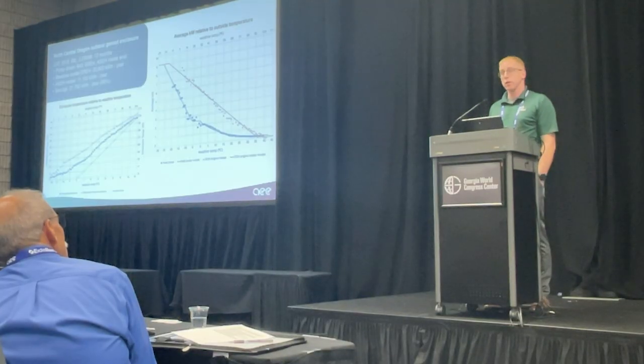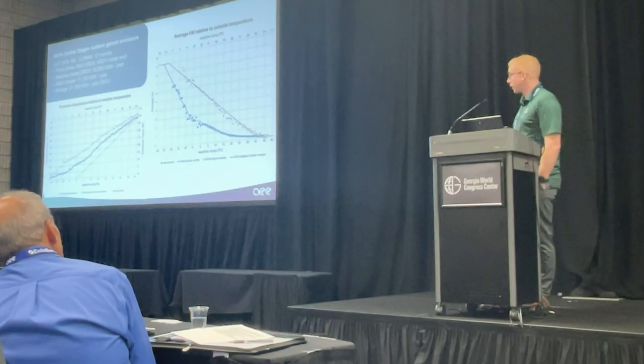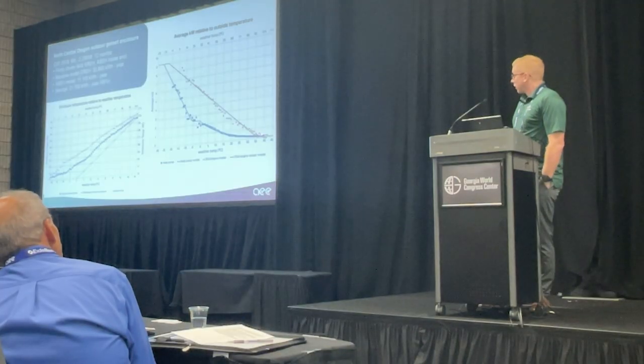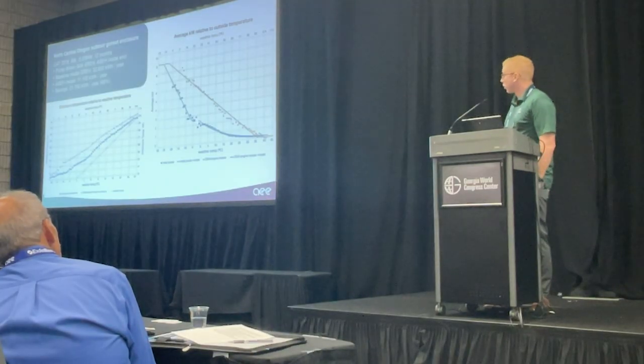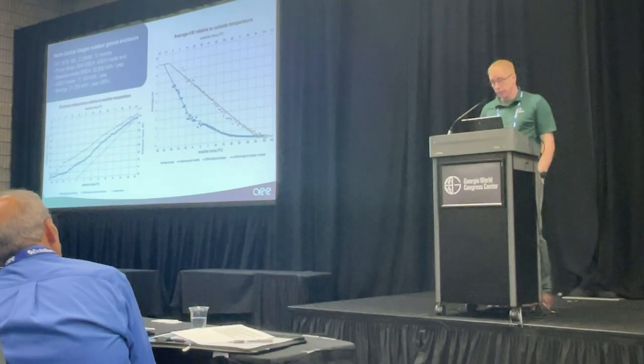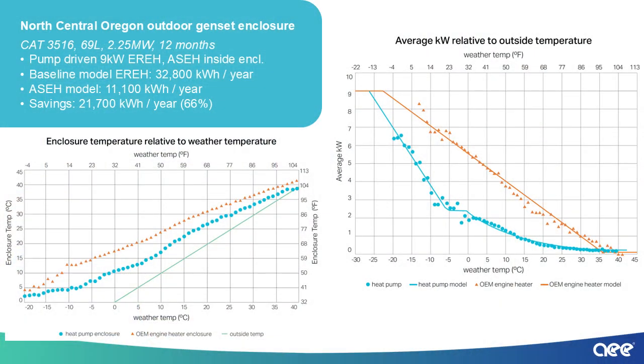So if you're looking at the efficiency, if it was installed outside instead of inside, it would have operated more inefficiently, because you benefit inside the enclosure from the higher temperature, which improves the COP. Data was recorded over a year, so we have a more complete model of this particular unit. You can see essentially the curve is more reminiscent of what we expect from a heat pump than the linear curve fits that were in previous case studies.